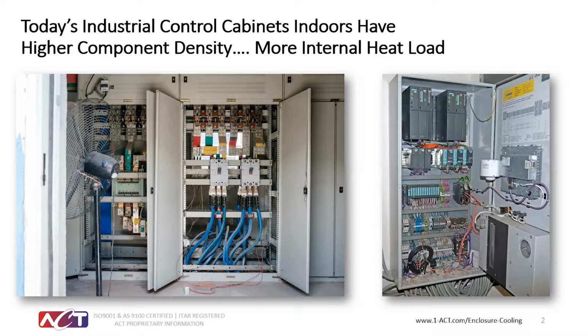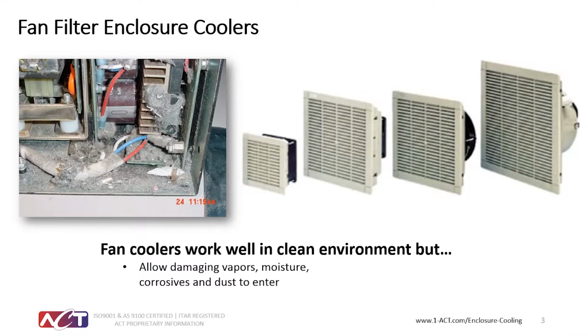contaminants, such as dust and aerosolized or sprayed or suspended chemicals. Additionally, some applications require frequent use of corrosive washdown, spray-down cleaning agents that can damage the outside and inside enclosure contents. Typically, fan coolers are incapable of keeping unwanted contaminants out of controlled cabinets because two cutouts, made for intake and exhaust air, are required.